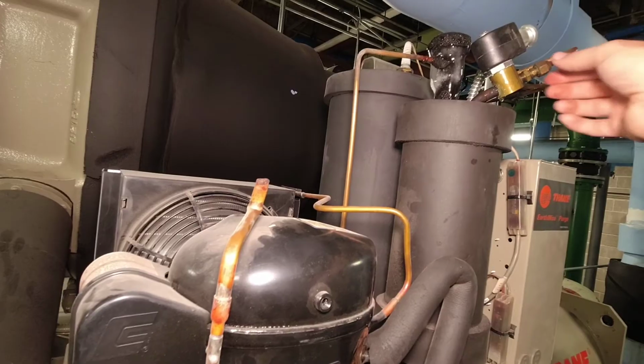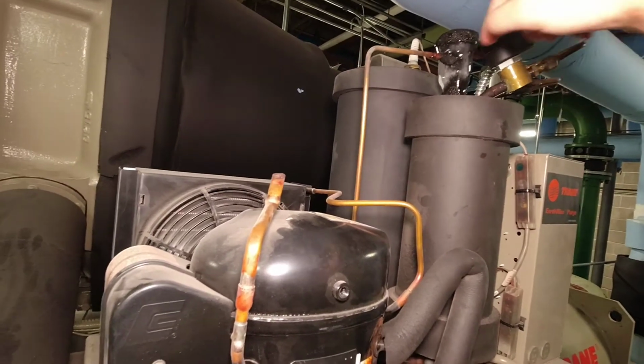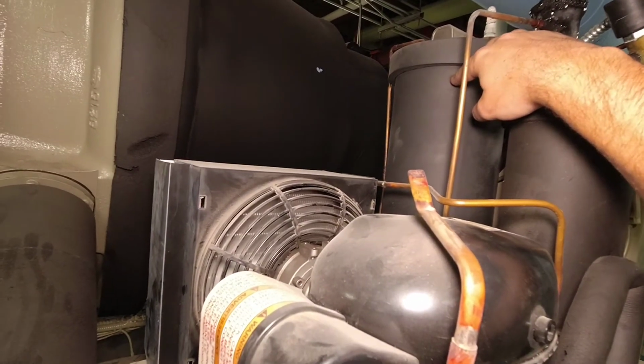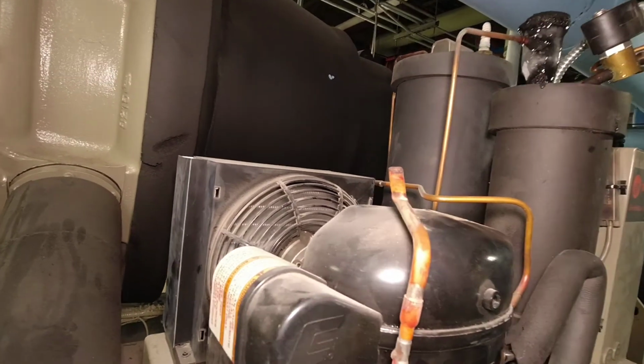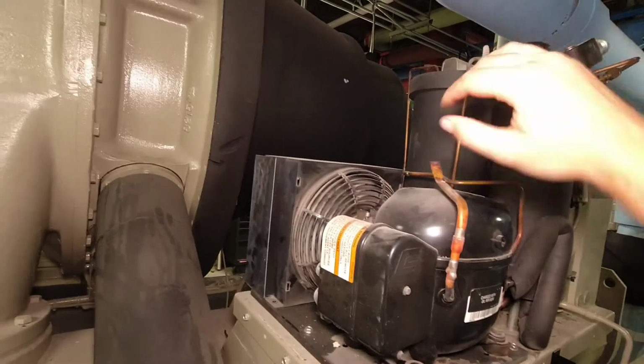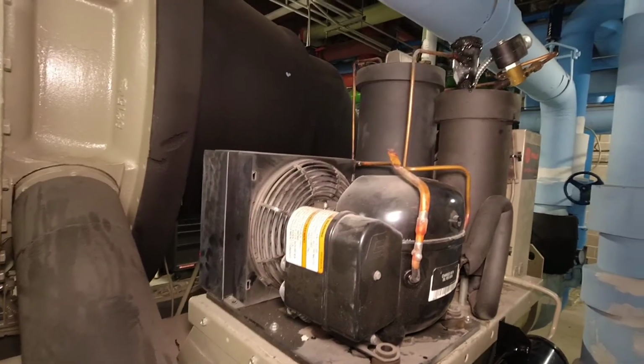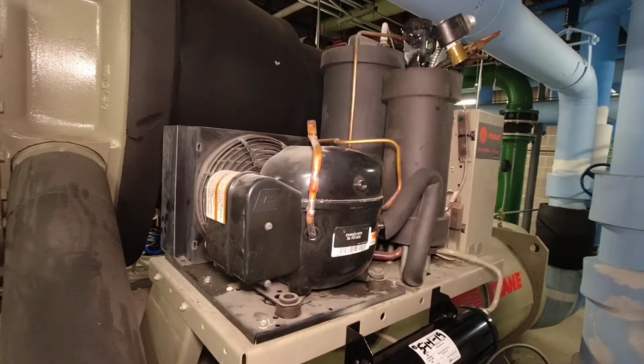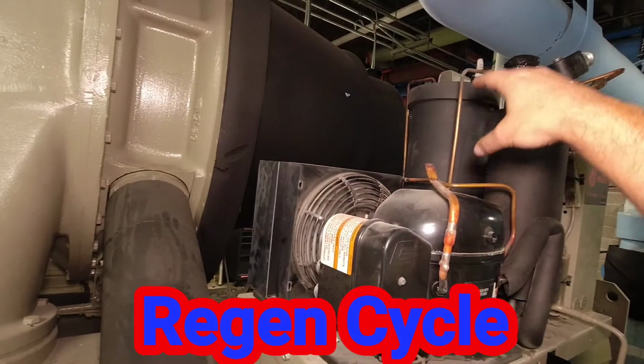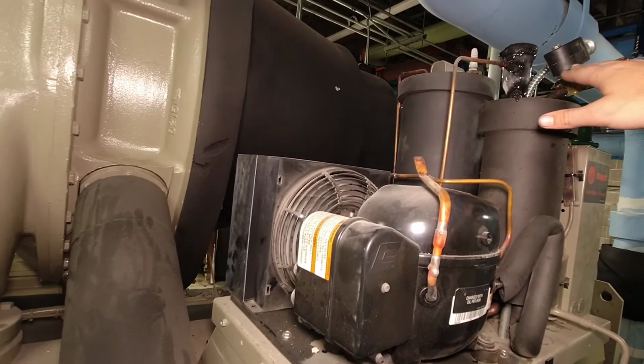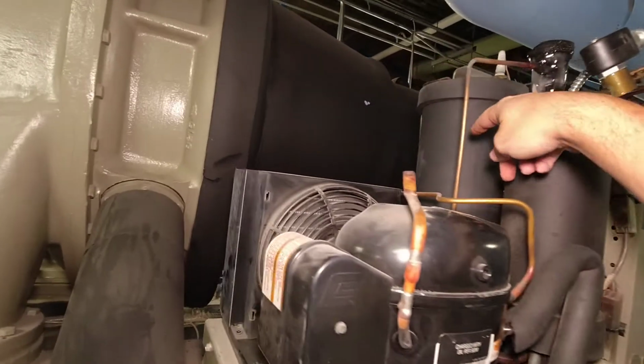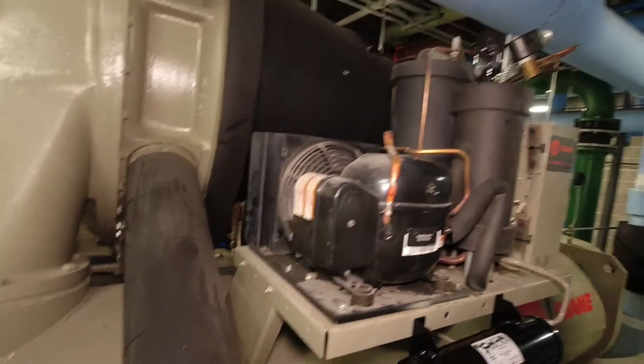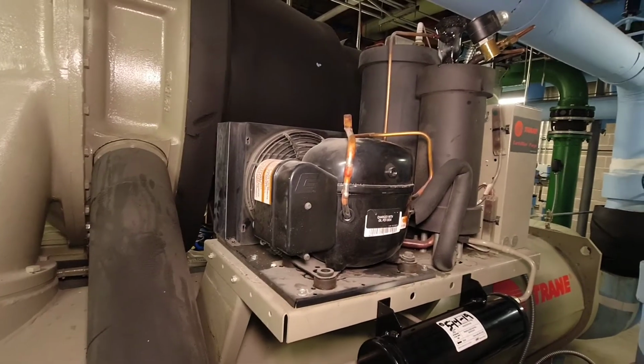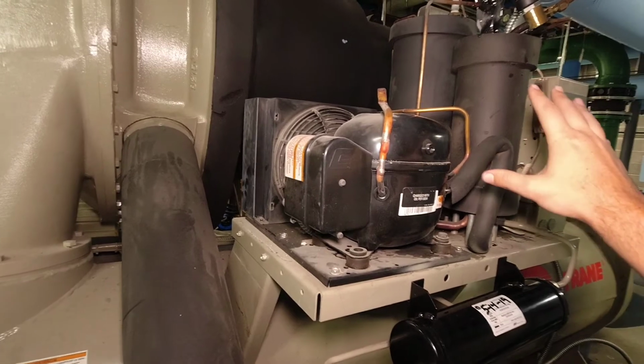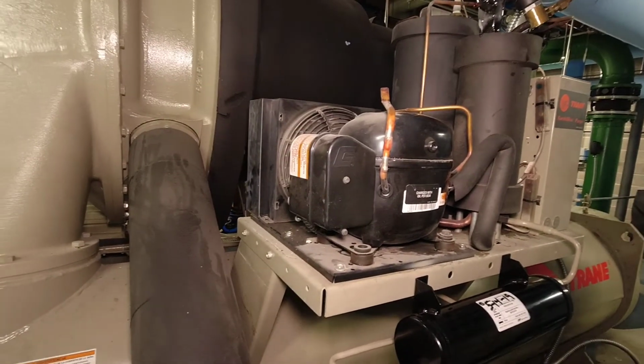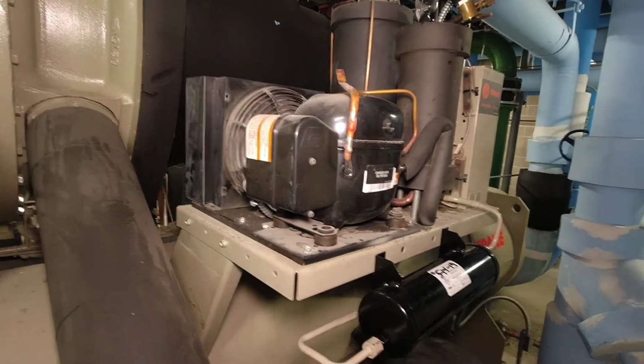So you will lose a very small amount of refrigerant from the system just through the pump out process. This regen tank's job is to collect that refrigerant through a filter, and those molecules bond to it, and the atmosphere is allowed to pass through with a minimum amount of refrigerant possible. So every so often this tank has to go through, I forget the exact term the factory uses off the top of my head, anyway, what it does is it doesn't pump out like it would traditionally. What it's trying to do at that point is heat that filter in there up with an element to, I think it's 120 degrees or 140, something like that. It heats that element up hot enough so that the refrigerant molecules unbind and flow out back into the chiller and can be put back into the system.